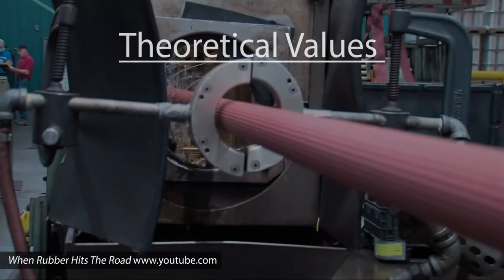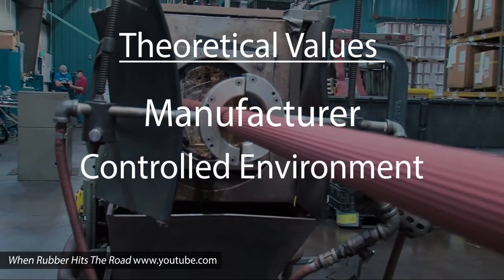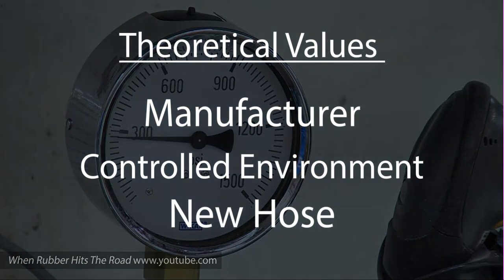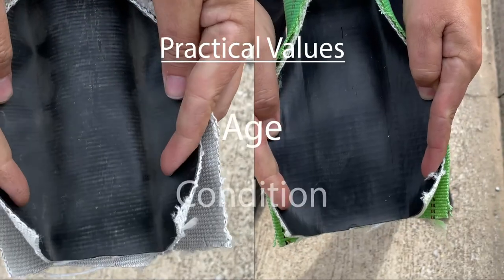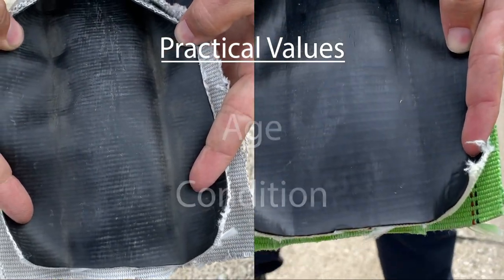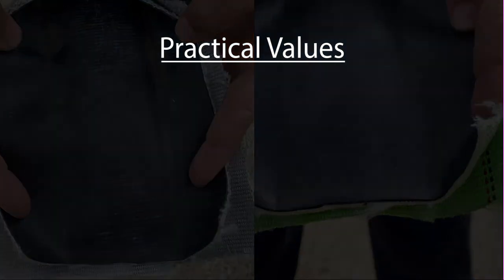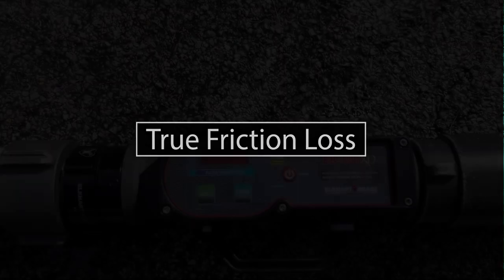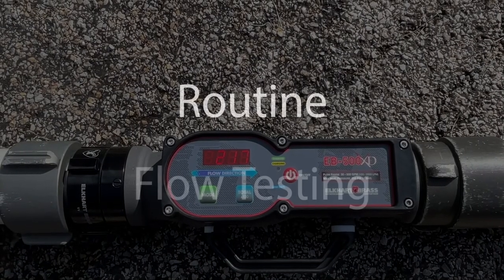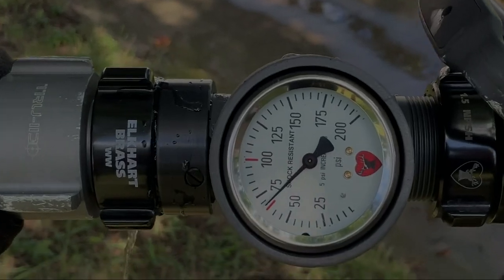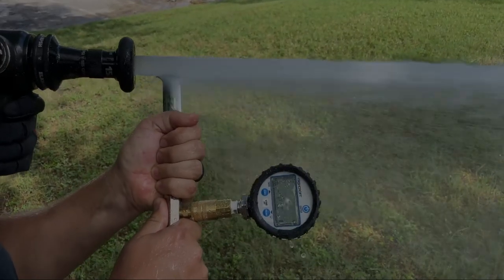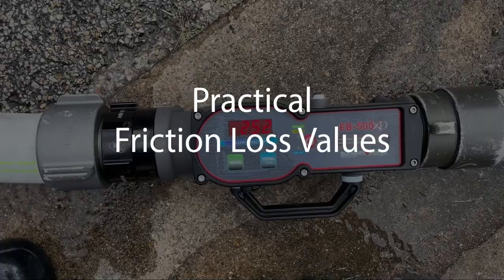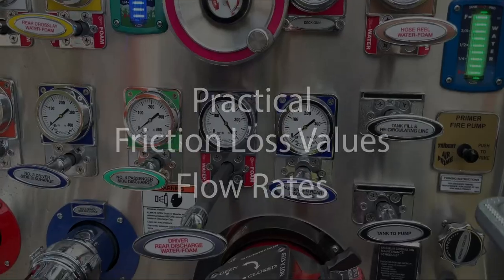There is one caveat to remember when calculating theoretical friction loss based on hose coefficients. These values are obtained by the manufacturer in a controlled environment using brand new hose. Depending on the age and condition of your current hose, it is very likely that the true friction loss for your hose will vary significantly from theoretical models. The only way to truly identify required pump pressures, adequate volume, and accurate friction loss values is to perform routine flow testing of your apparatus. This allows operators the opportunity to obtain practical friction loss values and flow rates at a variety of pump pressures and hose lengths.